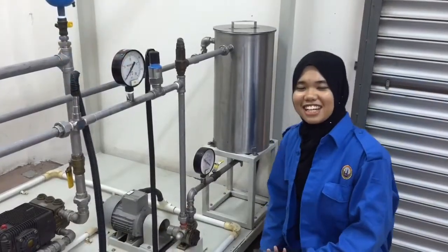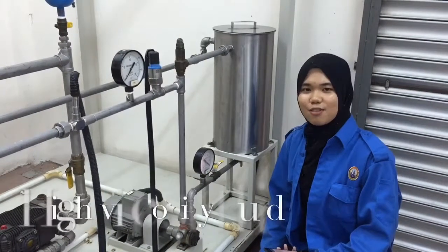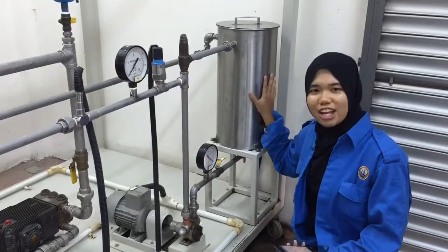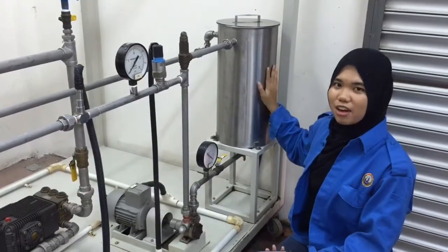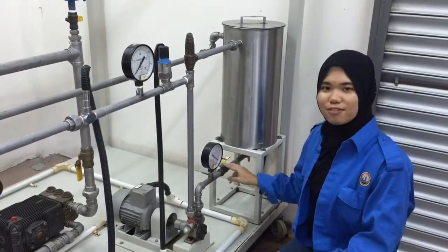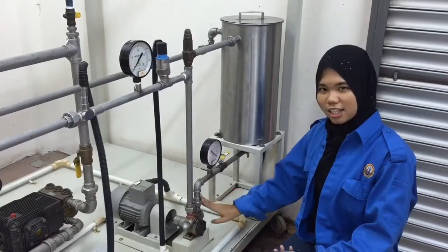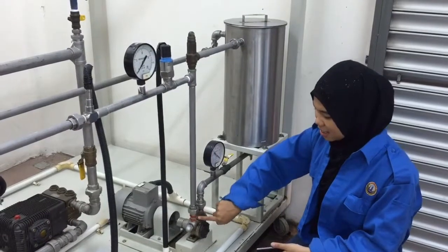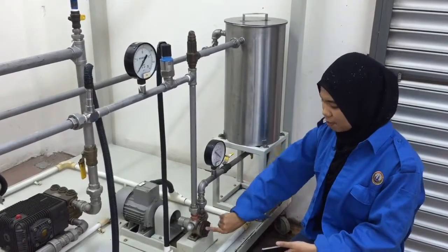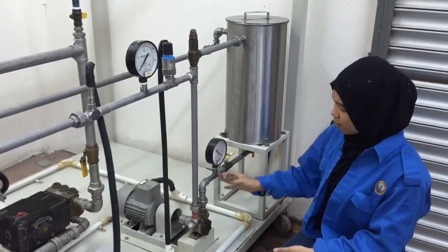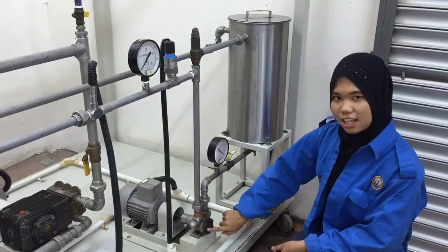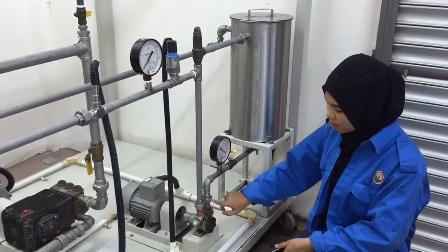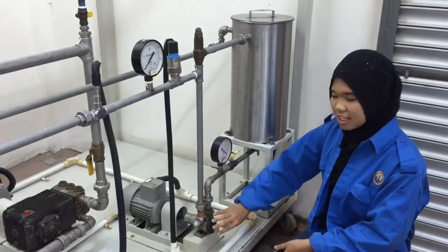First of all, gear pump uses a high viscosity fluid, which in this experiment is hydraulic oil as the flowing fluid. So hydraulic oil in the tank flows through the valve tank into the gear pump. So this is the suction port and this is the discharge port for the gear pump. When liquid flows through the pipeline, the liquid is trapped inside the rotating gear where it is forced from the suction into the discharge.